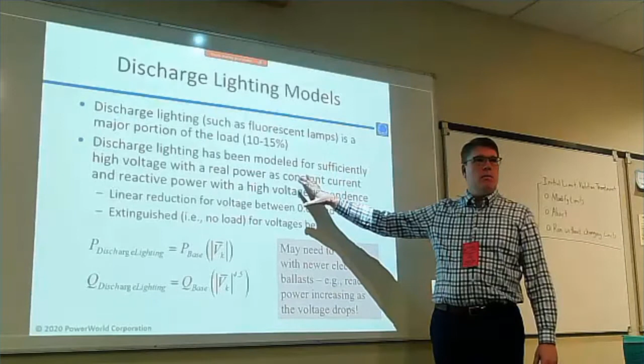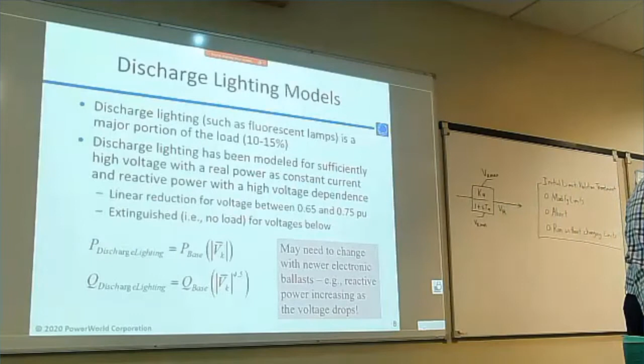This is a plot out of a paper showing different coefficients for different kinds of bulbs or power. This is kind of old - this is the old discharge lighting where it has this power to 4.5. If you look, that's essentially modeling this - a very high exponent on reactive power. I think we probably came up with this model in the late 1990s, and by the time we started implementing it, it really wasn't useful anymore because the electronic ballast changed.